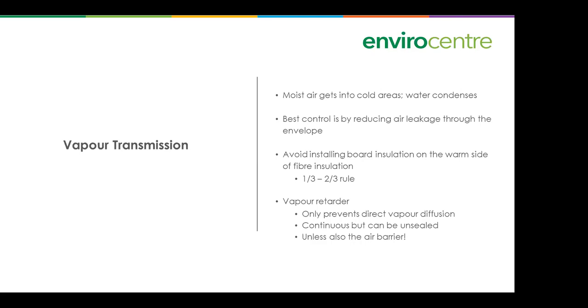But by and large, the way we're approaching this now is treating that as a vapor retarder, because we've determined it's more important to keep air from moving through the building envelope than to have an absolute vapor barrier. The problem is that moist air gets into cold areas and the water condenses. That's really the essence of the problem, and the best control is to reduce your air leakage through the building envelope.